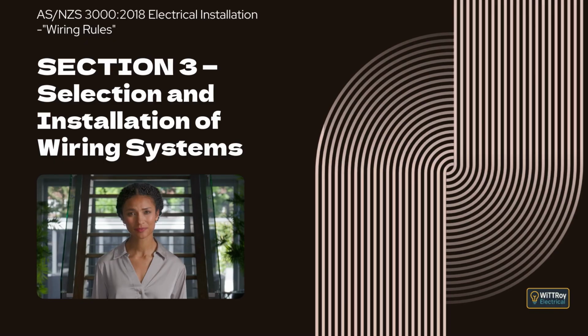Clause 3.9.3 Support and fixing. This clause introduces how wiring systems must be physically supported and fixed. Clause 3.9.3.1 General. This clause states that wiring systems must be supported by suitable means and fixed using clips, saddles, clamps, or similar devices that do not damage the cable and are not adversely affected by the wiring materials or the surrounding environment. Where wiring passes through building elements, openings must not weaken the structure below the limits required by building codes. Where sheath cables pass through metal structural members, edges must be treated to reduce abrasion. Where disturbance is likely, cables must be fixed close to the opening. Certain exceptions apply where wiring rests on a continuous immovable surface or where alternative fixing methods provide equivalent strength and support.